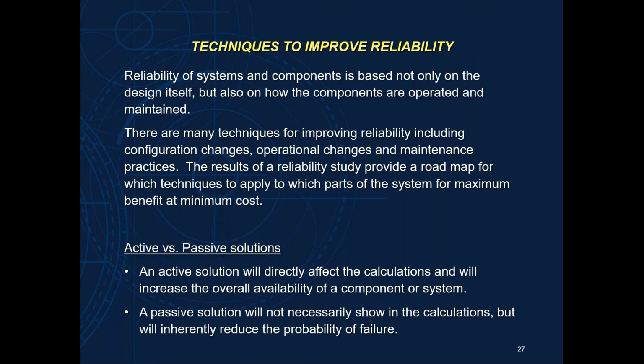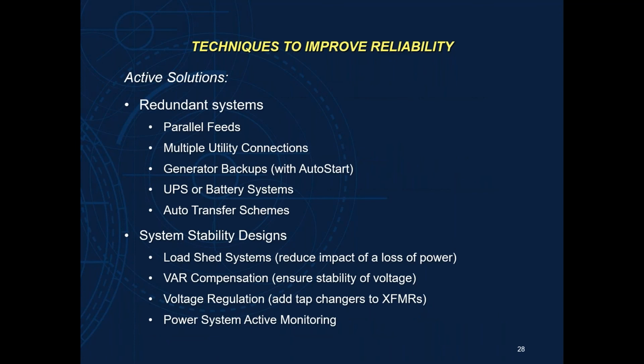So now that we've talked about that quickly, this is going to be very high level. What do we do to improve reliability? What do we have at our disposal? I'm going to give you a couple of quick active and passive solutions, as I call them. An active solution is something that we can actually measure with the calculation. We can come up with a concrete calculated value and see the benefit. The passive solution is something that doesn't necessarily go into the calculation, but we know inherently will improve our system reliability. Active solutions: parallel feeds, adding generator backups, backup systems, transfer schemes, those are important.